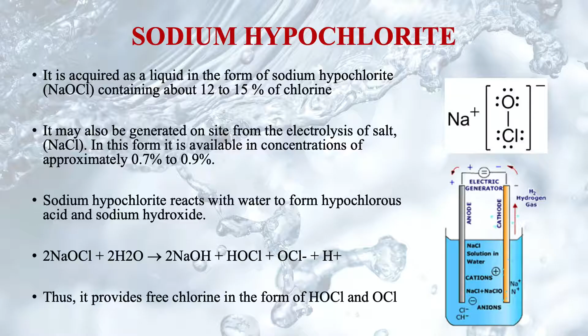The advantage of sodium hypochlorite is that it has similar disinfectant efficiency and residual performance as chlorine gas. The added advantage is that it reduces the hazards associated with handling and storing of chlorine gas, especially if generated on the site. With on-site generation, sodium hypochlorite solutions are less concentrated and less hazardous than the standard supplied solutions. As compared to chlorine gas, it is relatively cheap and can economically disinfect small to large amounts of water. Then if kept under sealed conditions, its shelf life is not a factor. It can be easily stored for about a couple of months.